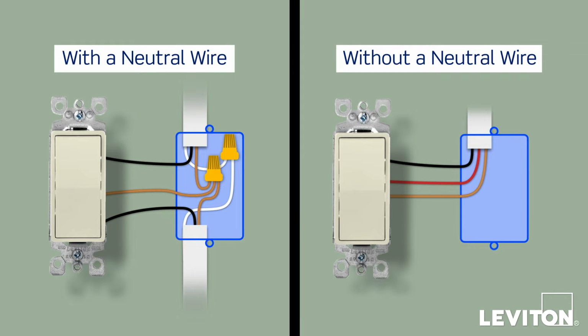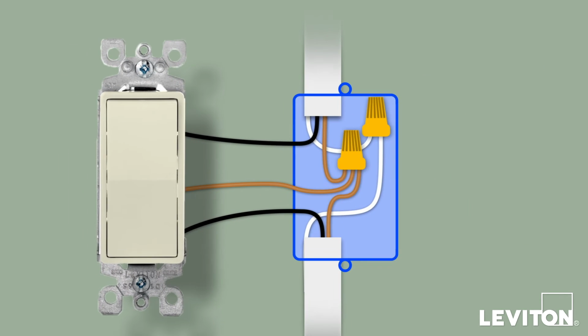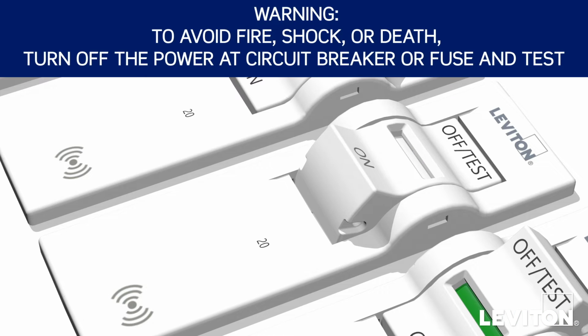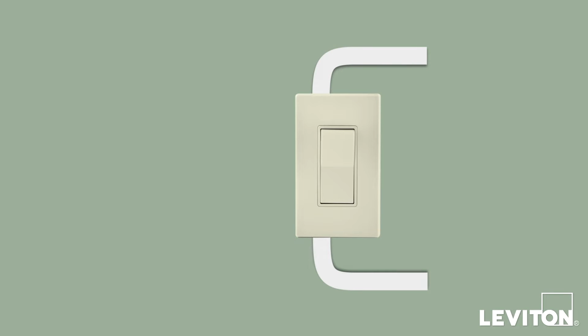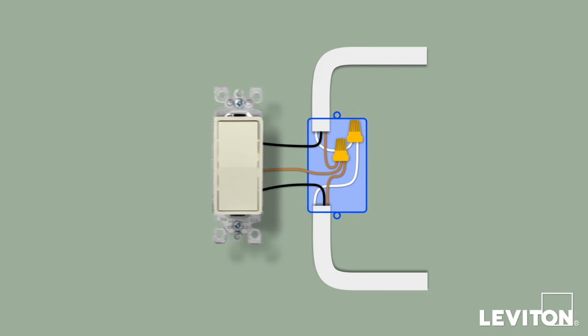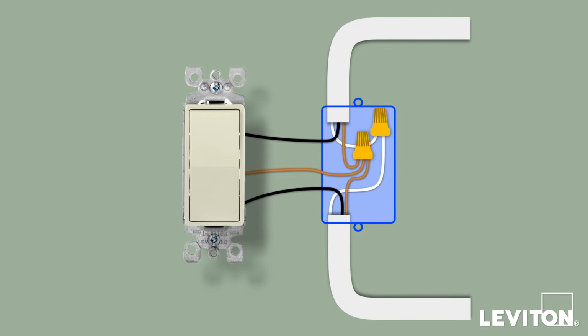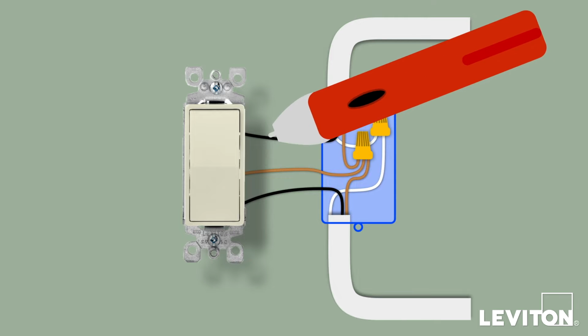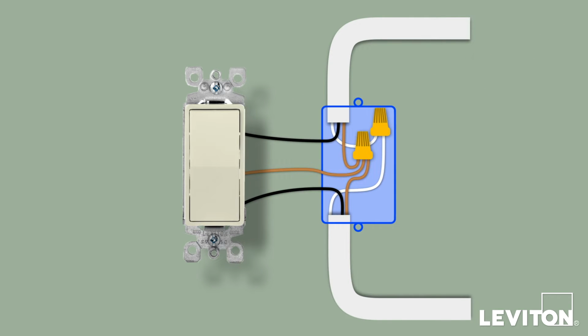If you're not sure if you have a neutral wire, you'll need to look inside the wall box to identify if a neutral wire is present. Start by turning off the power at the circuit breaker. Remove the wall plate and carefully pull the device out until you clearly see the wires. Using a voltage tester, ensure that the power is completely off.